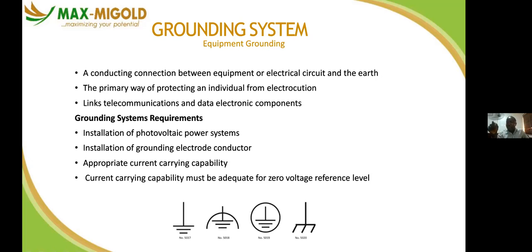Most of the time I get 0.00 something, like 0.004. So you have to improve it every time, I mean. But it's recommended you do it twice a year. Hello, sir. Hello, when you say improving, do you mean tightening all the cables? Tightening them? No, it could be that there's a partial current along the line. The cable is not properly firm. It could be that there's a high resistance of soil there. What you do is dig around it and pour salt and water around that place. It will lower the resistance.